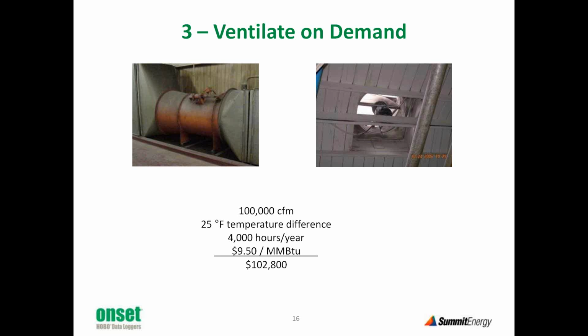But now here's what happens. Maybe it's a Friday afternoon, not a lot of people showed up for work, or they're all out doing something, not that many people in the office. The CO2 level starts to drop. The HVAC controls, or the ventilation controls, see that the CO2 levels are dropping, and they bring in less outside air. Now, who cares? Well, it turns out to make a huge difference.